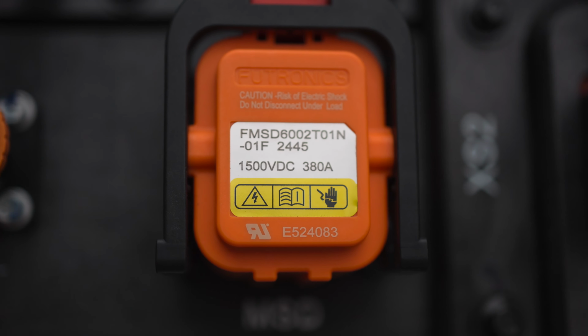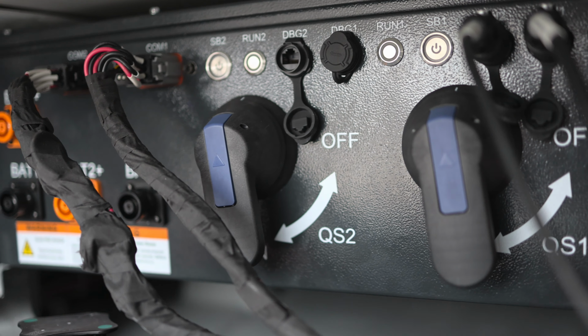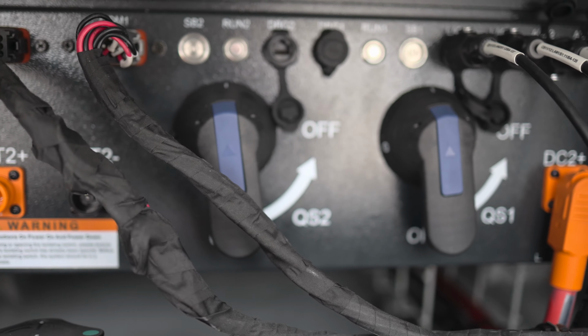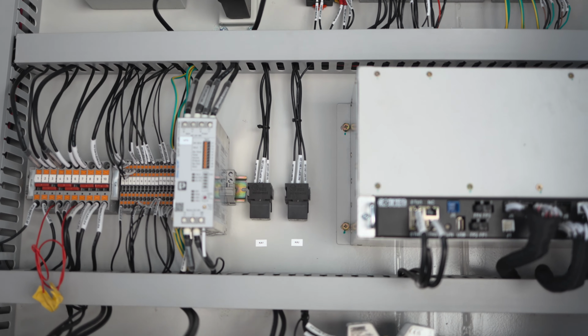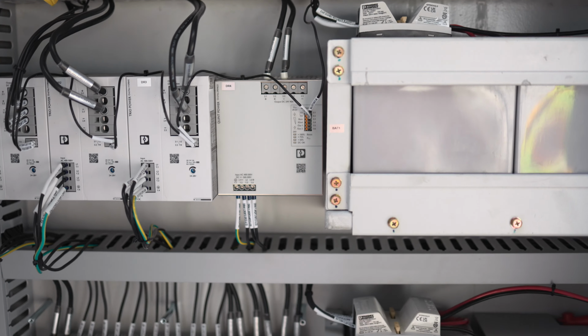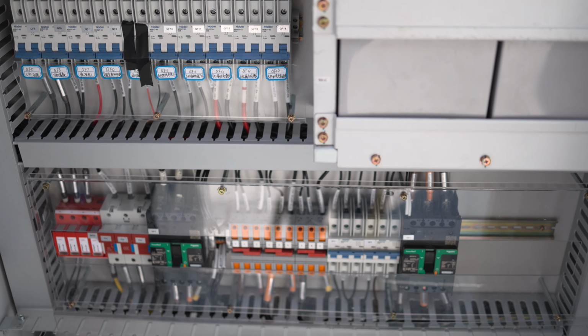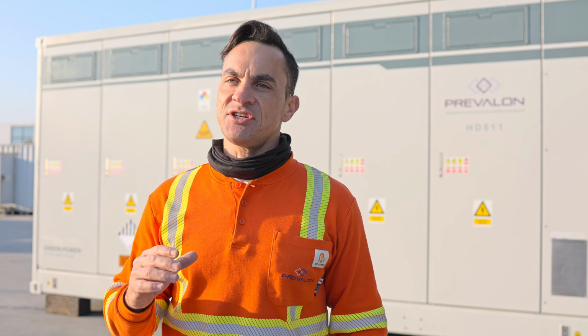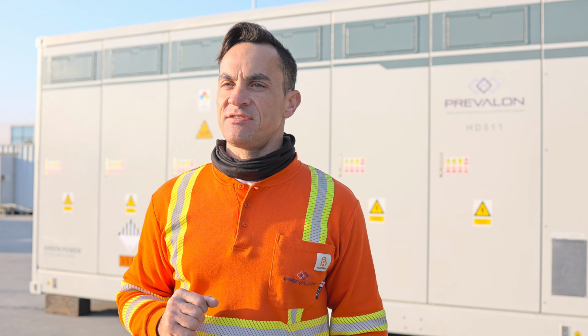Number 3 is electrical safety. We use properly sized high-speed fuses and circuit breakers to protect both DC and AC circuits. Each battery string has ground fault monitoring, and every field galvanic connection is equipped with a surge protection device.